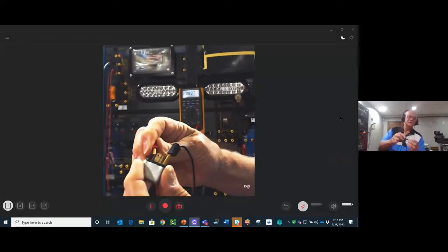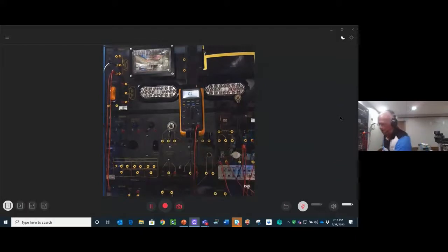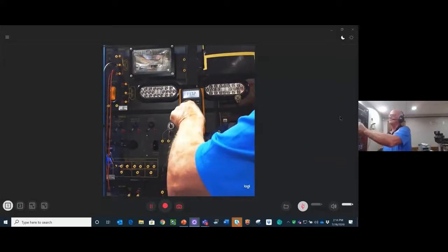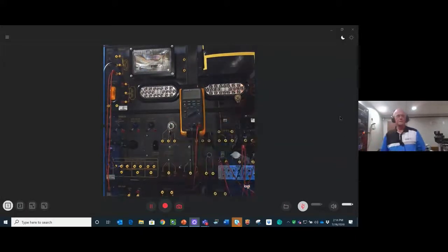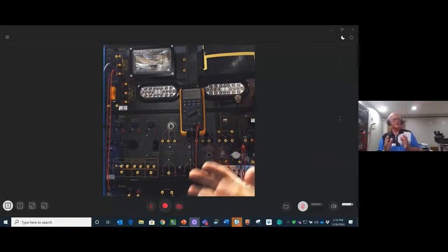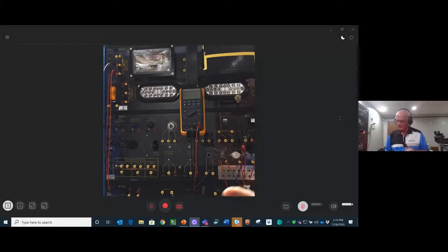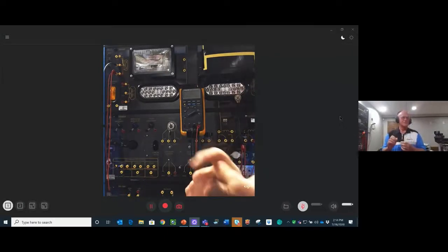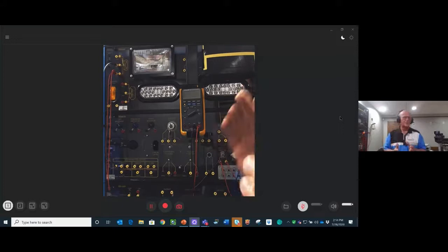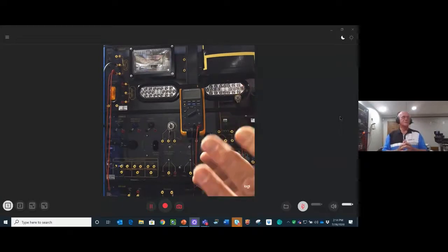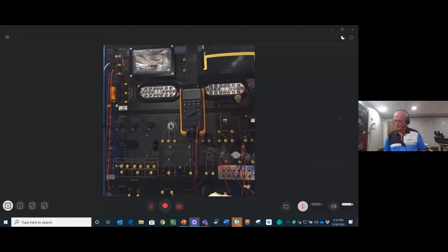Exactly the same reading (82.8). So you cannot use an ohm meter to determine if there's a diode in the relay. So that's how to tell, and that's how to test the diode. Now, if you simply hooked up 12 volts and ground to that relay coil and it had a diode, you would get a momentary little spike in the voltage or the current, the diode would open up, and the relay would still function normally, even though you no longer have any spike suppression.